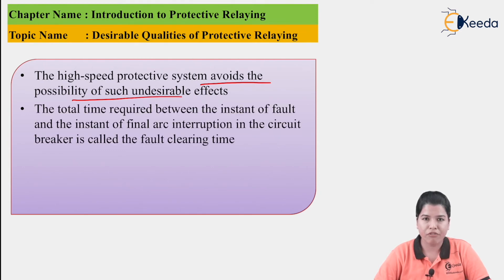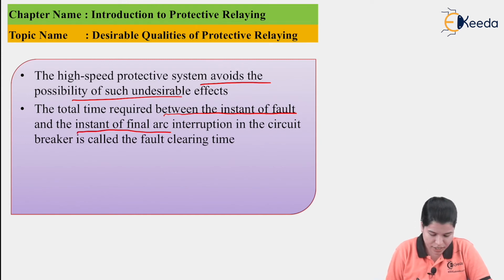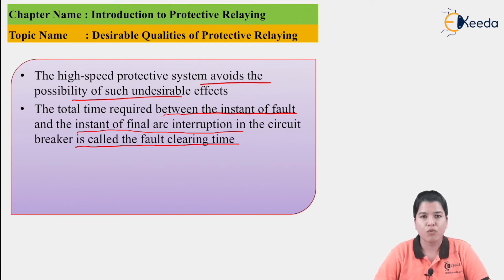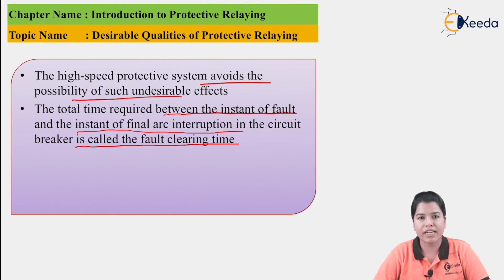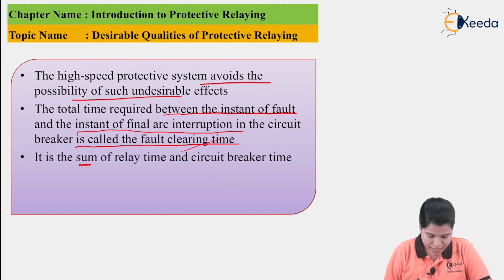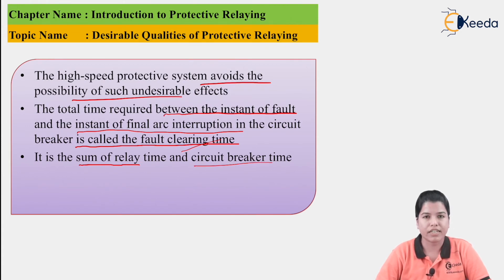The total time between the instant of the fault and the instant of final arc interruption in the circuit is called the fault clearing time. Once the fault occurs, a signal is sent to the circuit breaker; from that point to the final arc interruption is the fault clearing time. The fault clearing time is the sum of relay time and circuit breaker time.